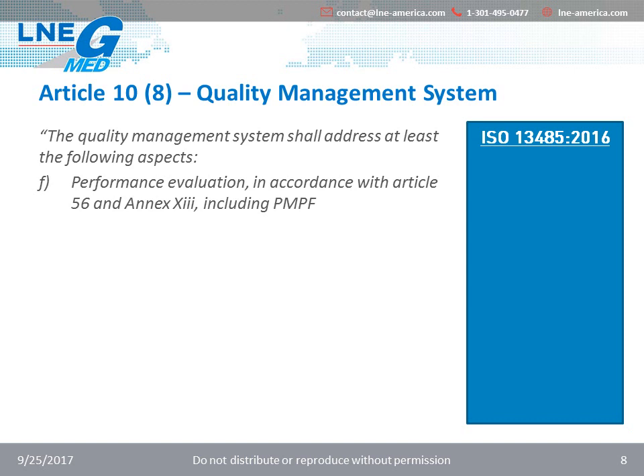This is directly related to Section 7.3.7 of the ISO 13485:2016 on design and development validation, which requires the organization to perform this performance evaluation of the medical device in accordance with applicable regulatory requirements. Here we see that we need to have a procedure in place and documented, where you would have the acceptance criteria and the method used to do the validation of design and development, which will come with the performance evaluation requirements of the regulation.